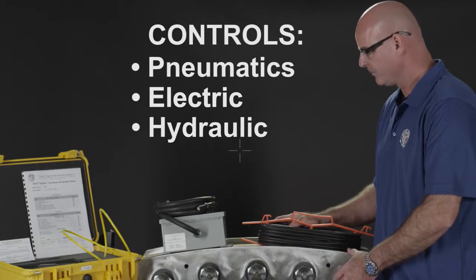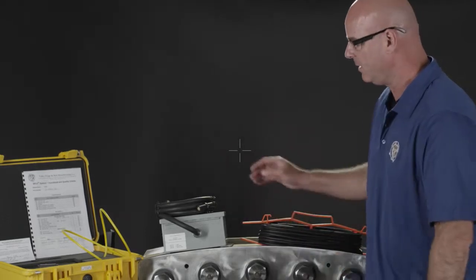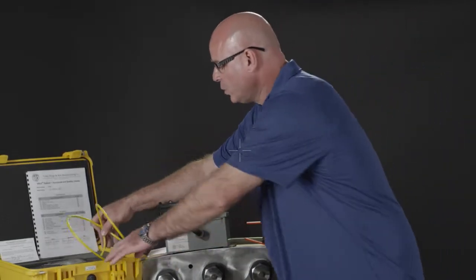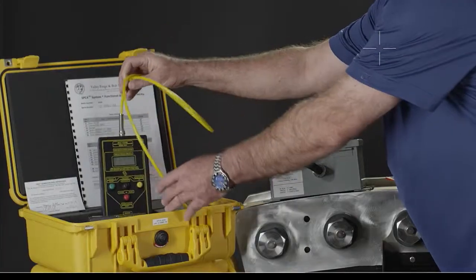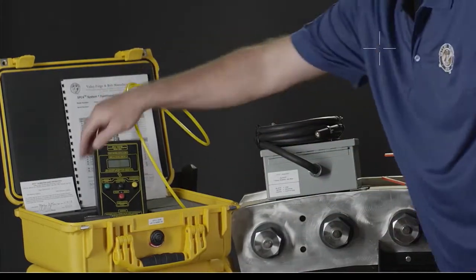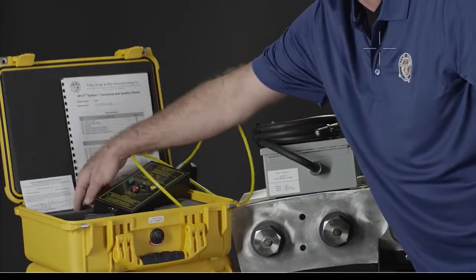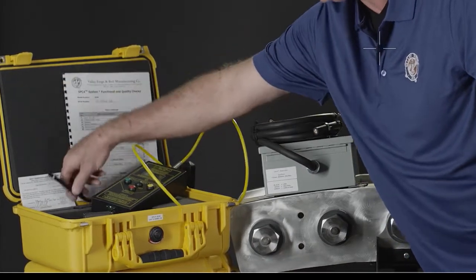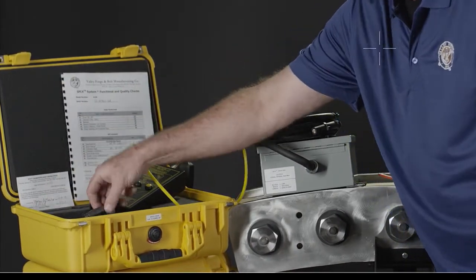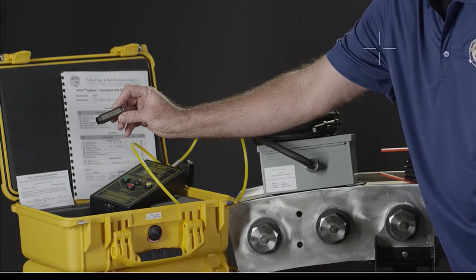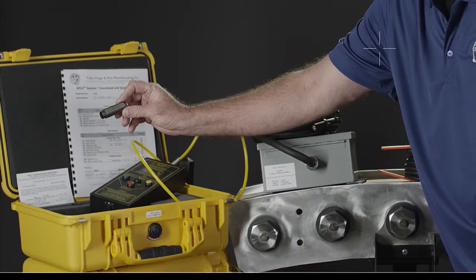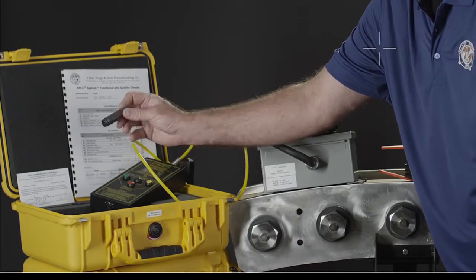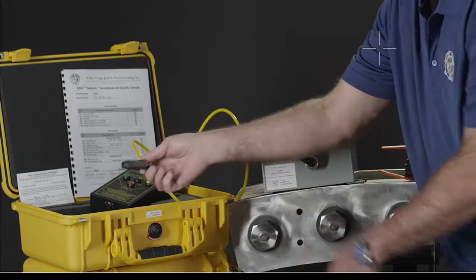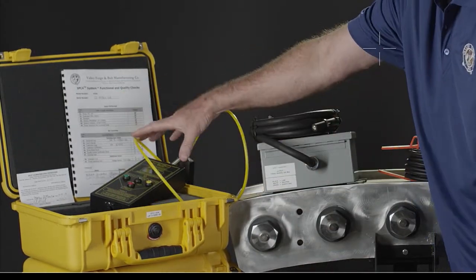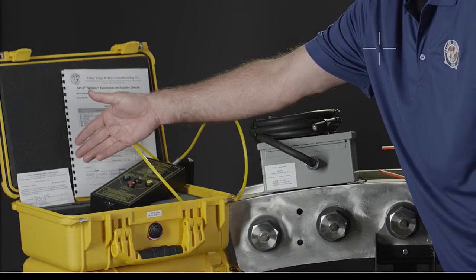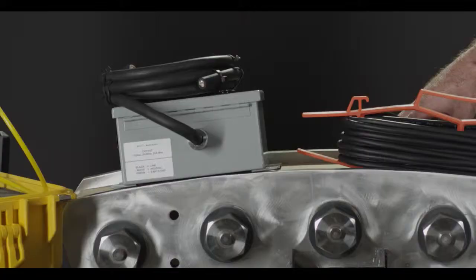Okay, so what does this kit entail? You have the SPC424 meter, and again, it comes in a kit style. So you've got the cleaning brush here in this pocket. You've got a SPC4 calibration gauge, and it was serial number 100 and 0 on it, so that you can make sure that the meter is reading correctly. It's got a certificate for that, and it has the instructions.